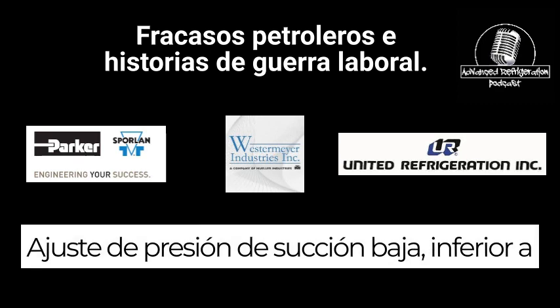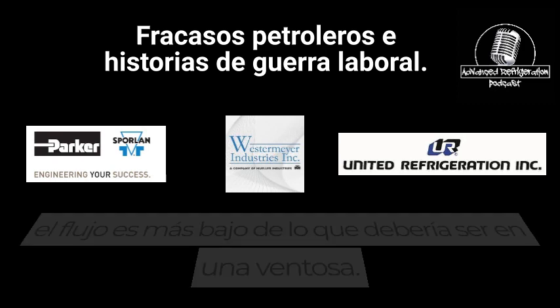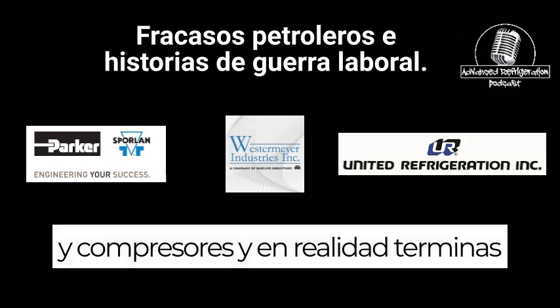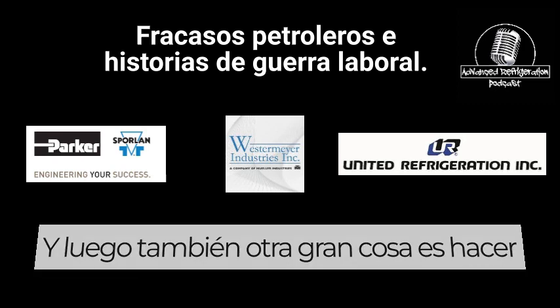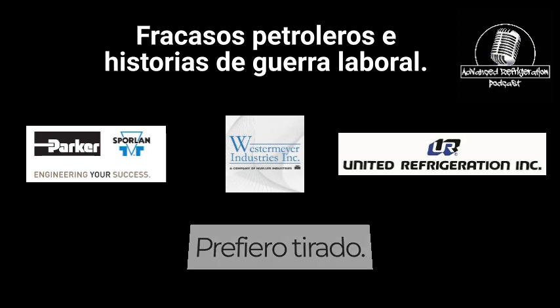Low suction pressure set lower than design, not floating at all, causes oil to not separate well, because now your mass flow is lower than it should be on the suction. So now you have less oil returning back to the compressors, and you end up causing less separation and less oil return. Another big thing is making sure your suction filters are clean and pulled. I prefer pulled.